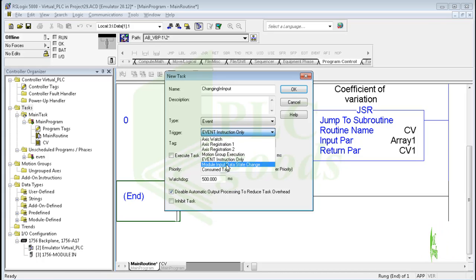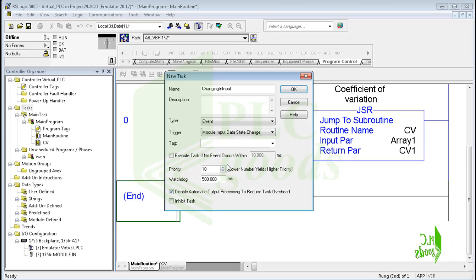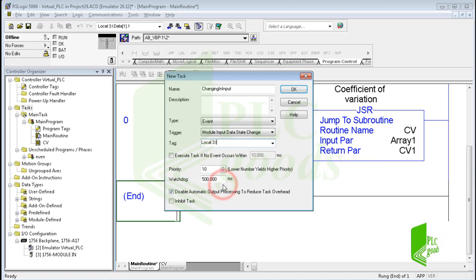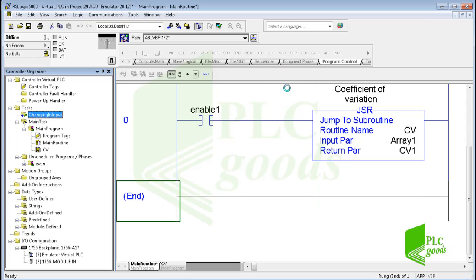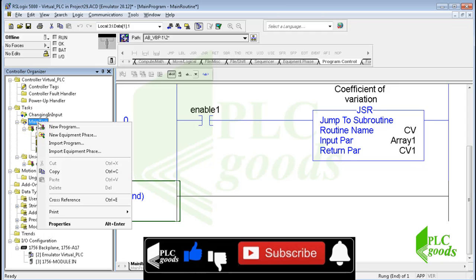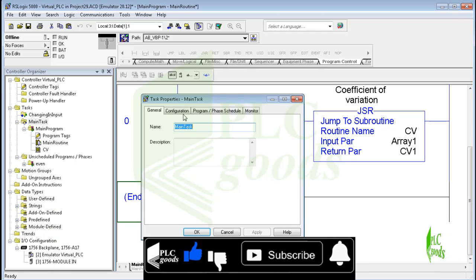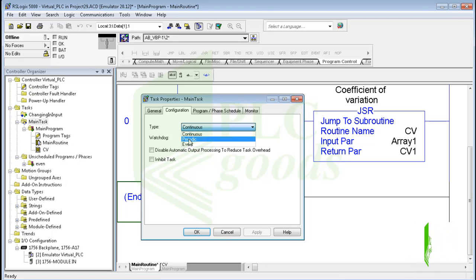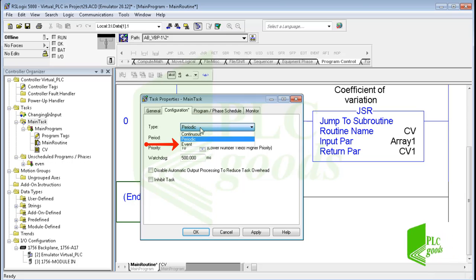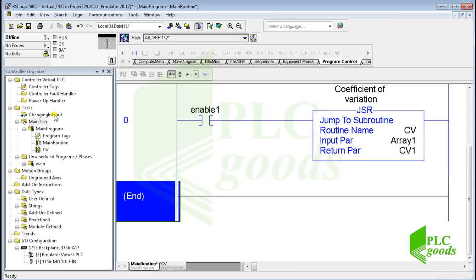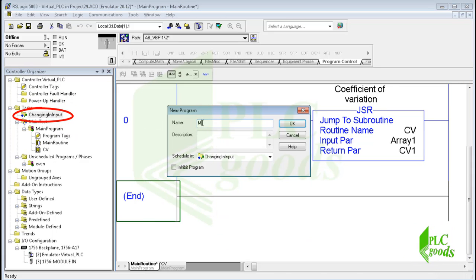Based on these settings, when the input module has any changes at its state, the new task will be executed one time. Note that there are three modes for each task: the main task — usually used to write the PLC program — is in continuous mode and executes continuously; a periodic task executes periodically; and the event mode I'm explaining now. Let me create a new program folder and a new routine inside the new task to write a simple program.